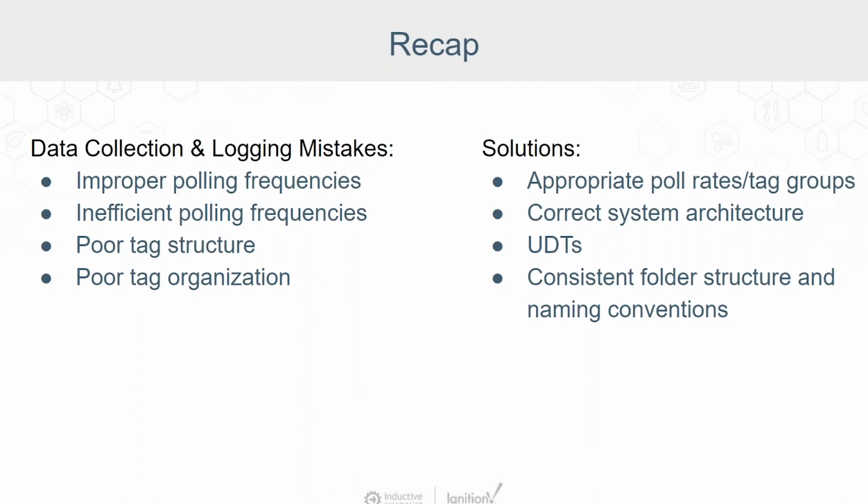rates and tag groups. This means that if you are connecting up to a PLC, say an Allen Bradley device, and you see all the tags and you just drag them in, it'd be easy to leave them at the default, which is once every second, when that's not necessarily appropriate for all of your tags.